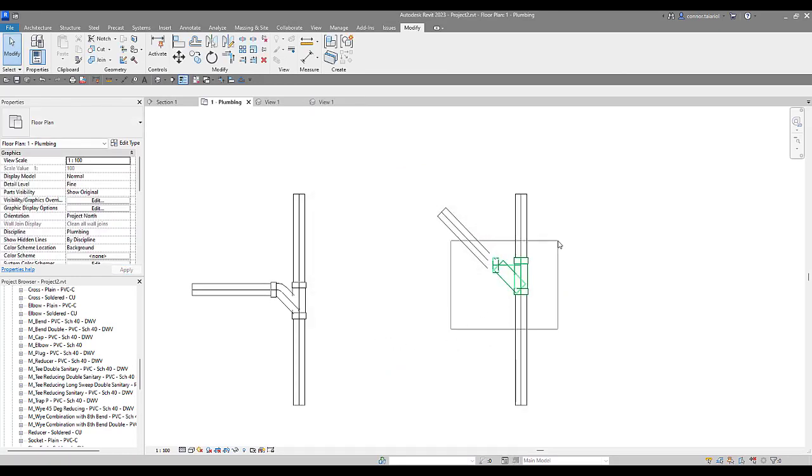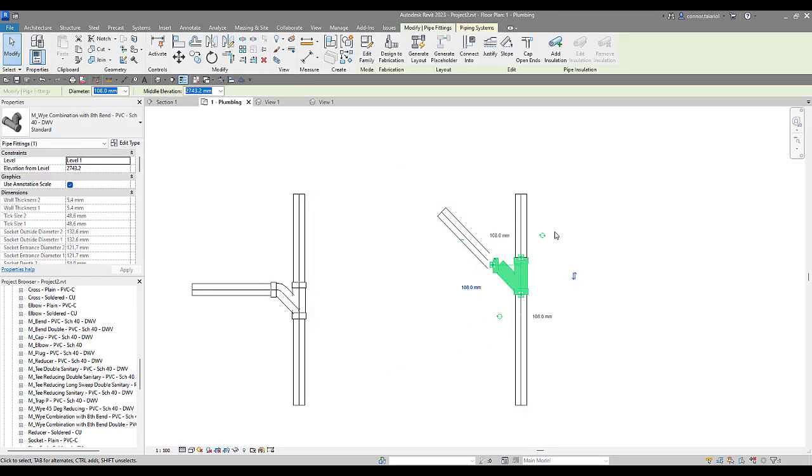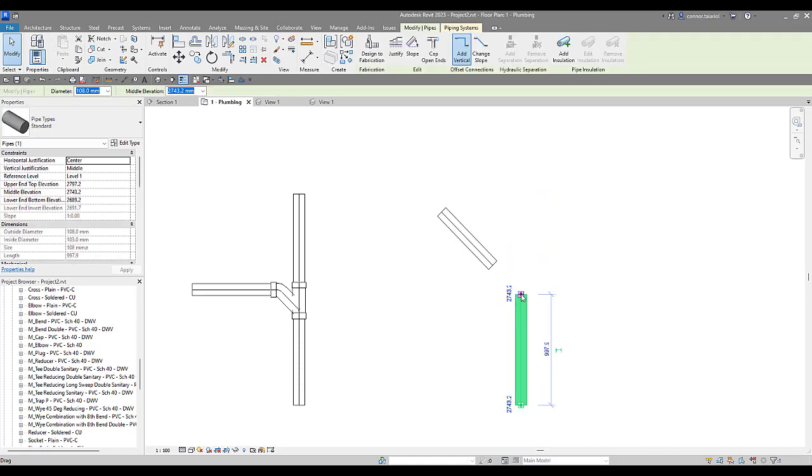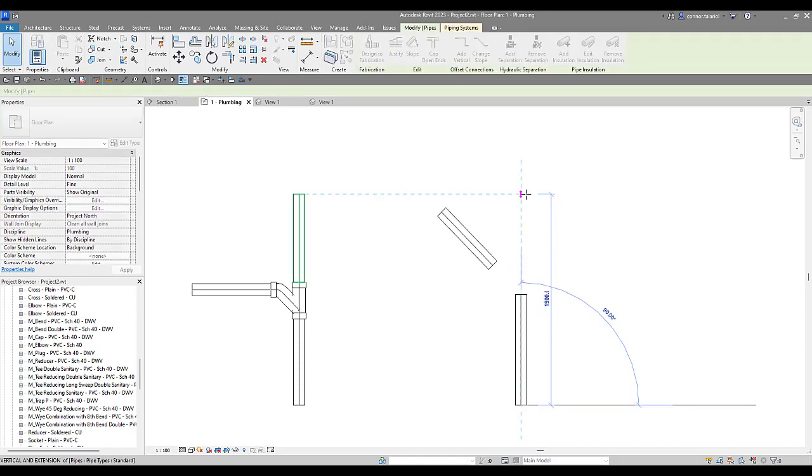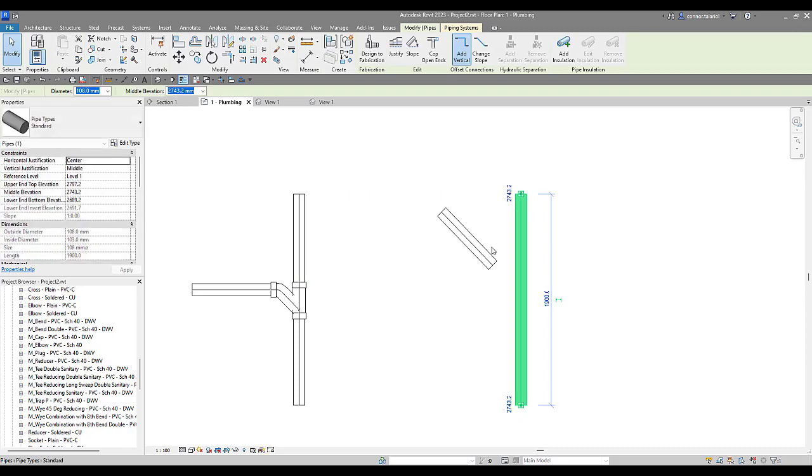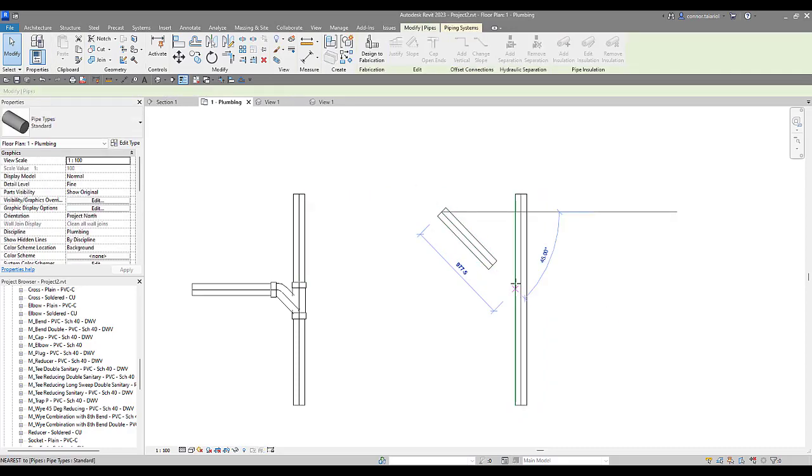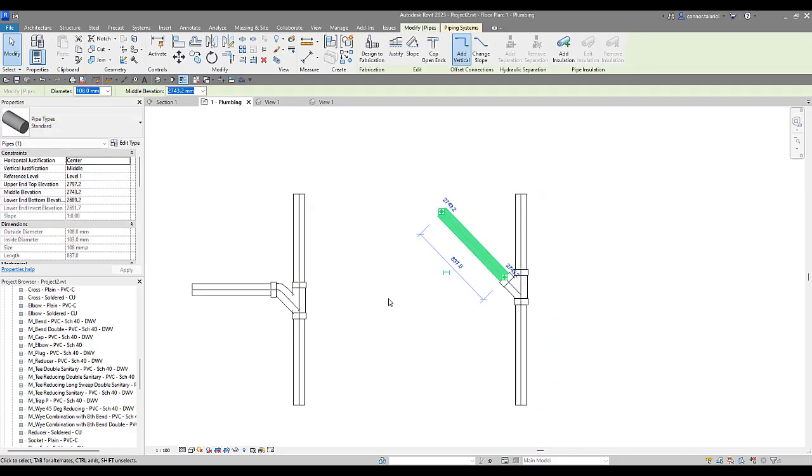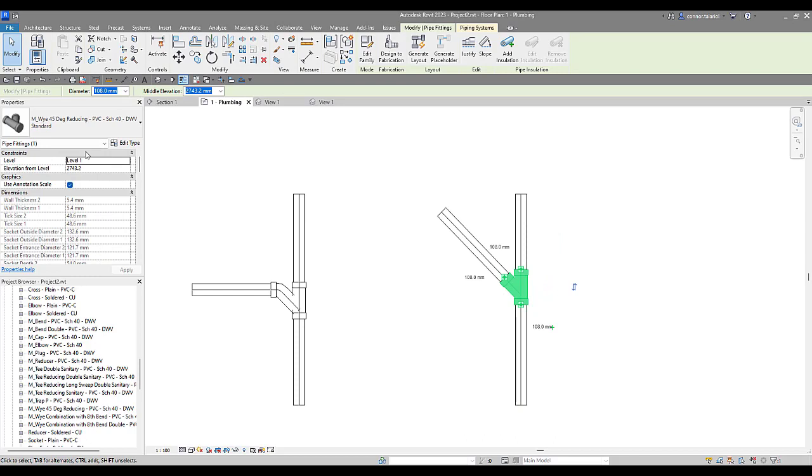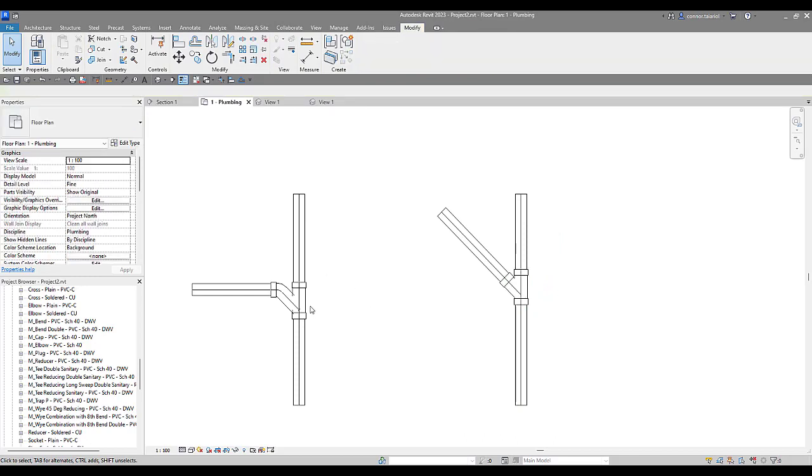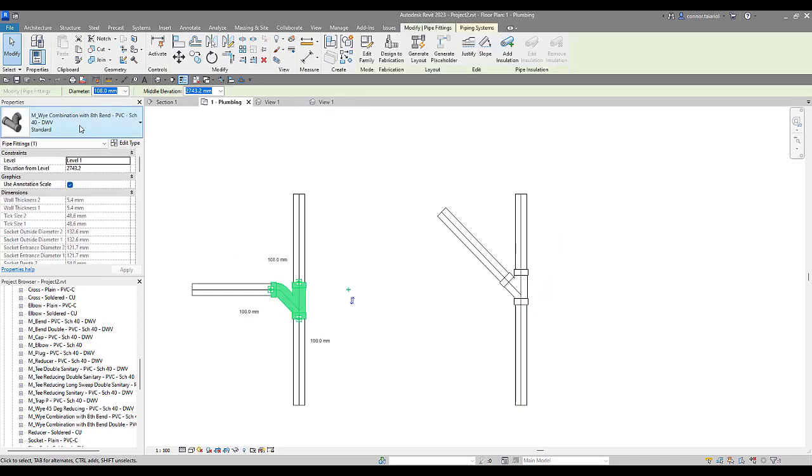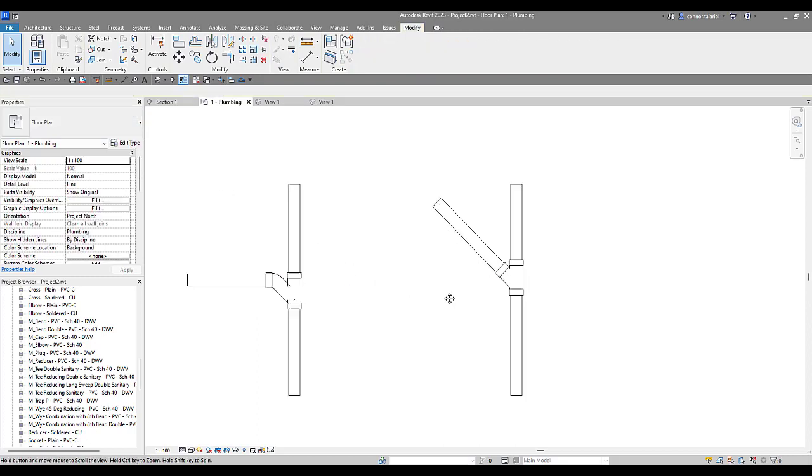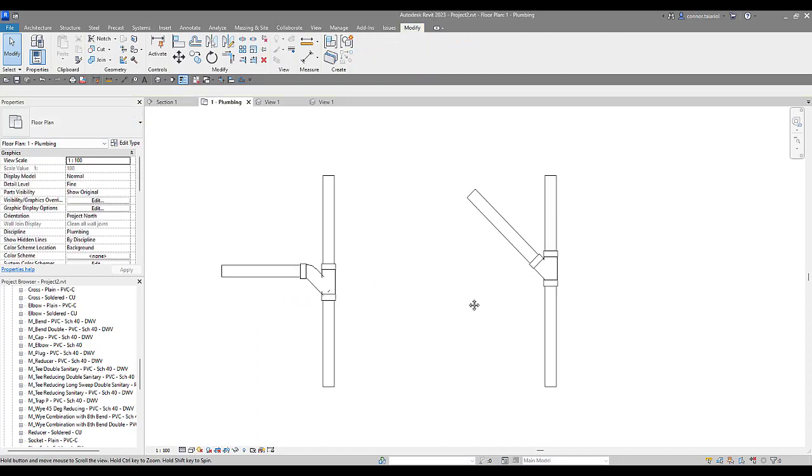I'm going to disconnect this one here. That's fine. We're going to have to redo that. Now when I come in I put this in at a 45. Now it puts in that 45 degree reducing instead of trying to put in the combination 8th bend. Nice and smooth.